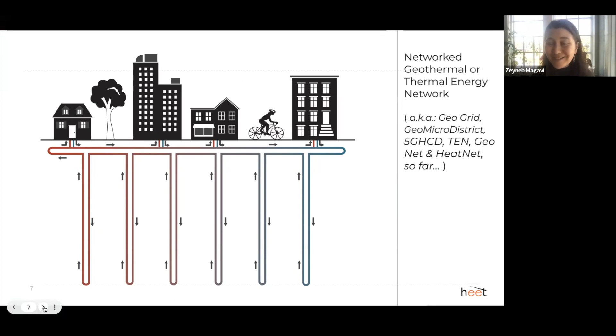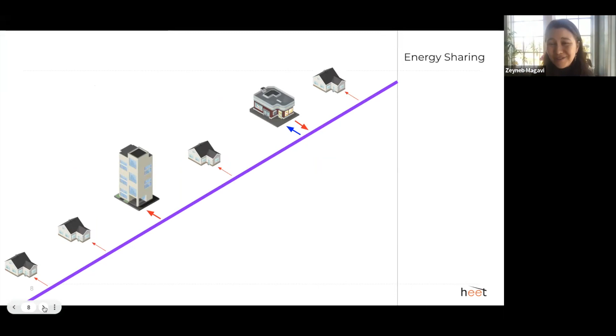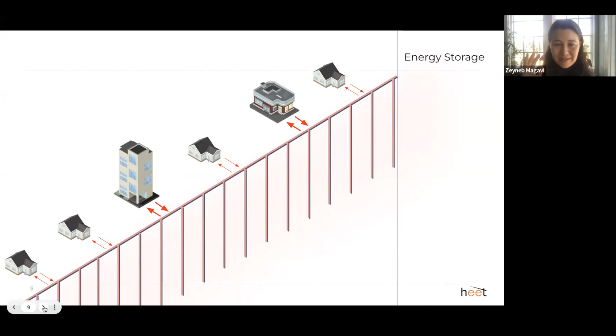Again, it is a networked ground source heat pump or thermal energy network, so it's got the shared loop between buildings and the borehole fields. I want to quickly explain why this means you get more efficiency on that load curve. That's because you're actually sharing energy between buildings, even without the boreholes. And when you add the boreholes, you're actually able to store energy so you can cancel the loads between buildings over time. That's how you're getting that crazy efficiency and load flattening for the grid.